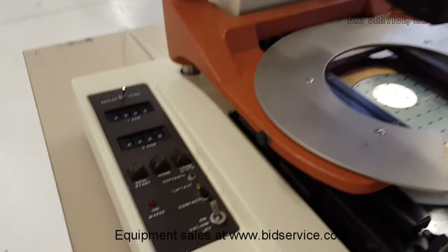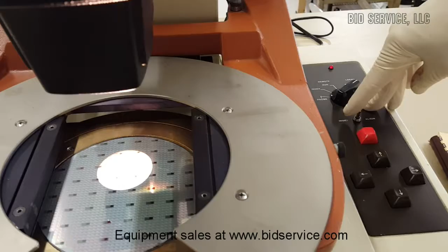I brought it to the home position. We have a switch over here: index, jog, and align. Normally, once you load the wafer, you need to align it, so you'll put that to the align position. Using these two arrows, you can move back and forth, and looking into the microscope, you'll adjust your theta using this knob, which is your theta adjustment, used while aligning.